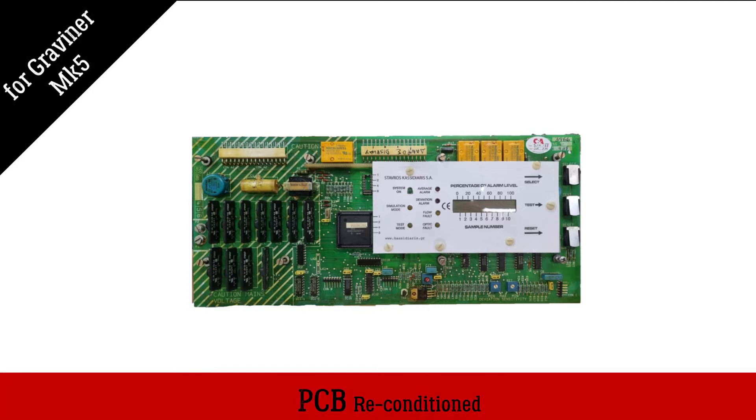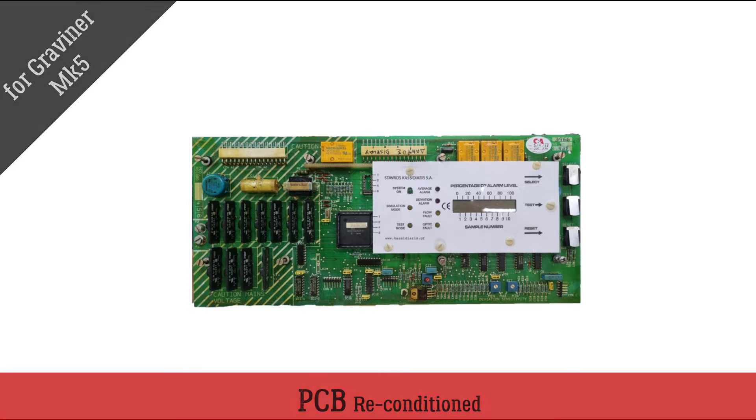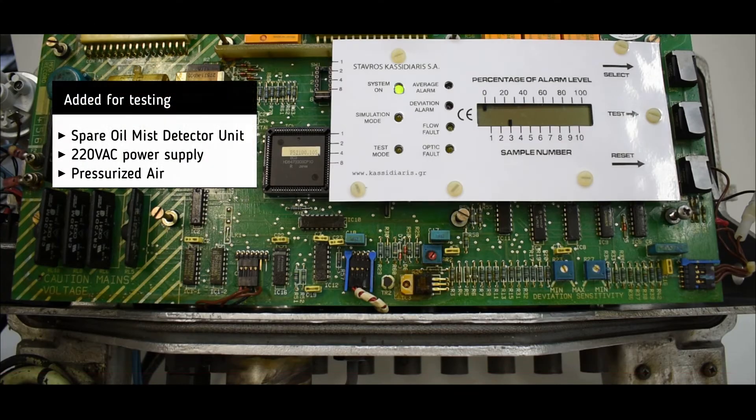Reconditioned PCB from Graviner MK5 oil mist detector. For testing, we connect the PCB to a spare oil mist detector unit. We add a 220 volt AC power supply to the oil mist detector unit and we perform a run test.